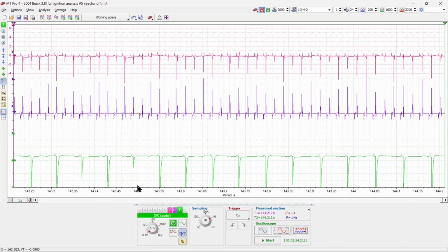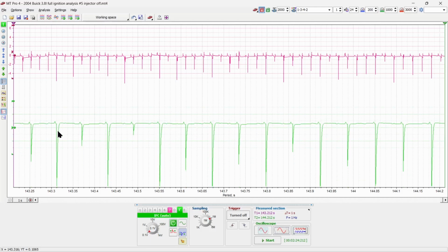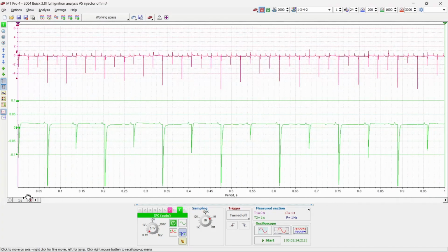The only problem that I've run into is sometimes it'll have issues with scaling, and I'll show you this here. So let's just turn off, take channel 9, we're going to move it up. I'm going to turn on the markings and the framework. So the framework shows our voltage limits on each end of the scale, and you can see how most of these, we'll go all the way back to the beginning too.